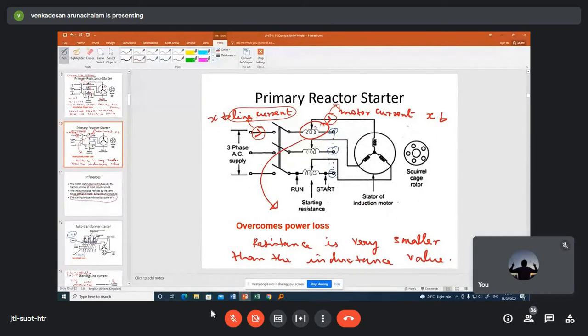If you connect all these three terminals, it becomes a star connection. You see here, this is the first reactor, this is the second reactor, this is the third reactor. So if you connect all these three terminals, it becomes a star connected auto transformer. And the stator also is in star connection. If you want, you can do a delta connection also. Delta connection means this should come here, this should come here, and this should be connected here. So a delta connected auto transformer also you can realize. So the concept is very simple in the auto transformer starter. If you connect the primary reactor starter either in star or in delta, depending upon the requirement and application, then it becomes an auto transformer starter.